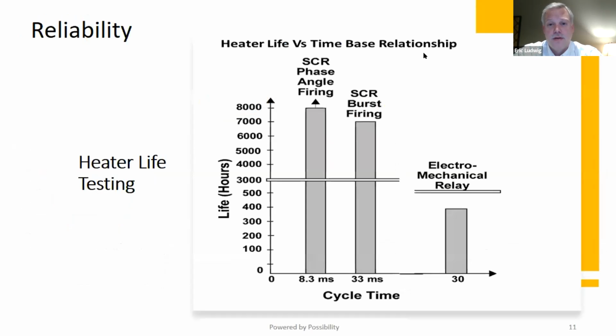Next slide, please, Dennis. So overall, we've done a lot of testing to understand heater life as associated with these different power switching modes. And you see that the SCR phase angle firing that we saw from the previous slide, that had the lowest element temperature, actually lasts longer than your other control modes within the system. Your SCR burst firing, which was very close in temperature to that SCR phase angle firing, lasted just about as long. However, these large swings, the sinusoidal swings in temperature that you saw with the electromechanical relay or the contactor type control, did not last very long. In fact, it was about 10 times less than your SCR control firing circuits. So this is just something that needs to be considered when going through and understanding what type of power control system you'd like to have to control your heating system. Next slide, please, Dennis.